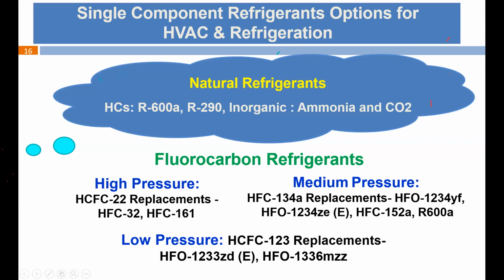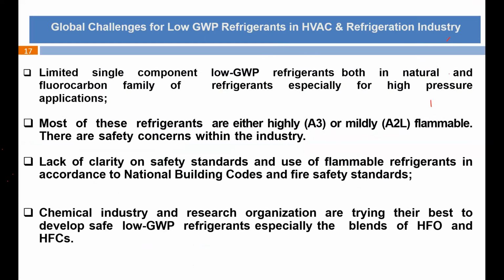And in the case of low pressure refrigerant, the replacement can be HFO 1233ZD or HFO-1336mzz, which is hexafluoro-2-butene. What are the challenges for low GWP refrigerants in the HVAC and R industry? Mainly these HFC and HFO refrigerants are now in the developing stage, and some manufacturers have already started, especially HFO refrigerant in chillers, but it is mainly still under development. Single-component low GWP refrigerants are very few for high pressure applications. In that case, those refrigerants are either A3 or A2L category, which is highly flammable or mildly flammable. So safety is a concern.